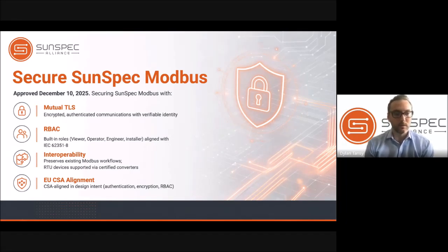And so it includes mutual TLS for encryption, and it preserves everybody's existing SunSpec Modbus implementations. So manufacturers and device people with SunSpec Modbus communication interfaces can continue to use their existing communication interfaces and use this to secure the traffic if it's done over a public network.